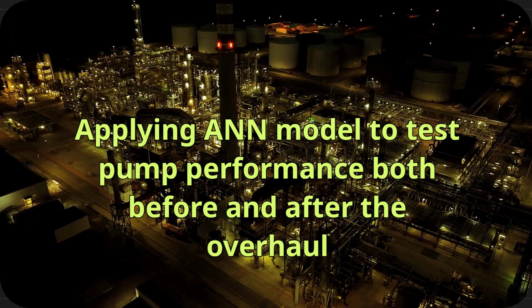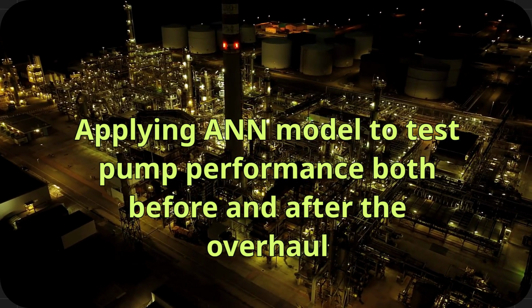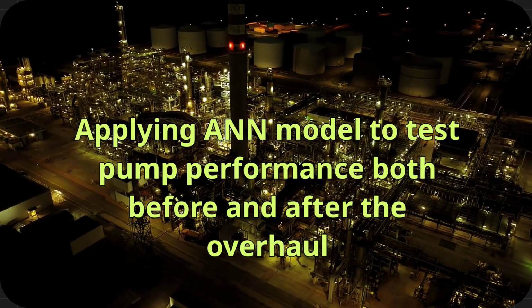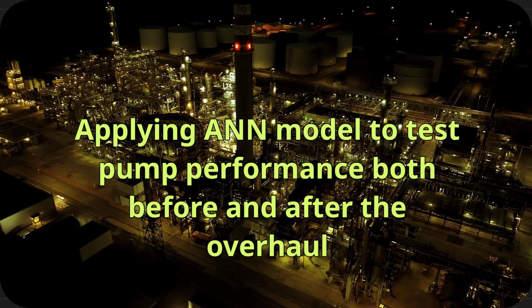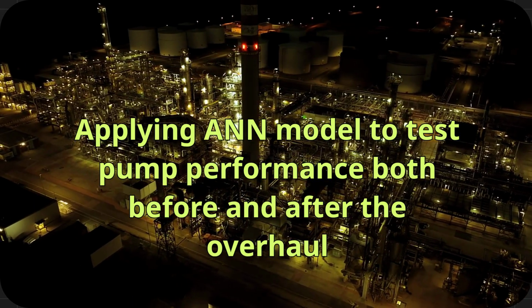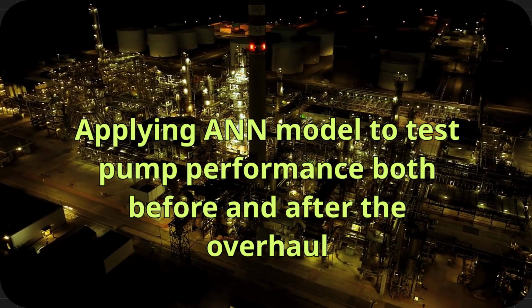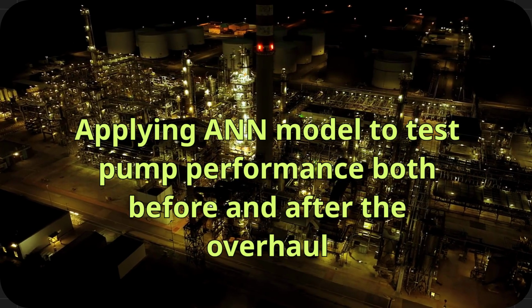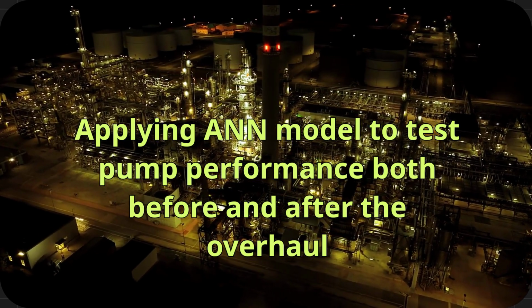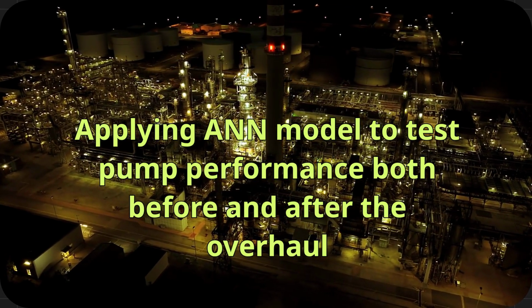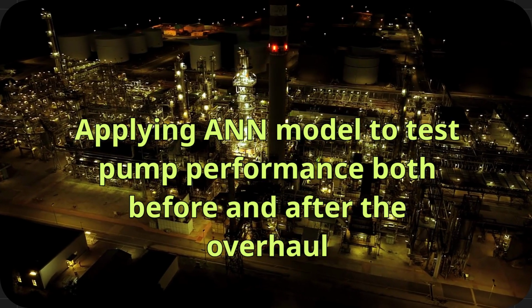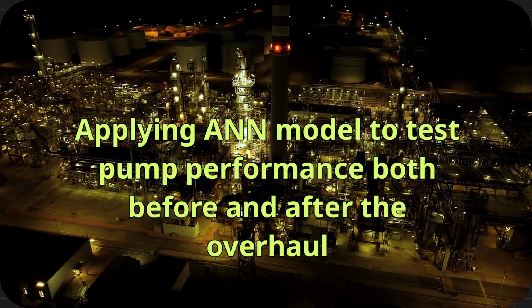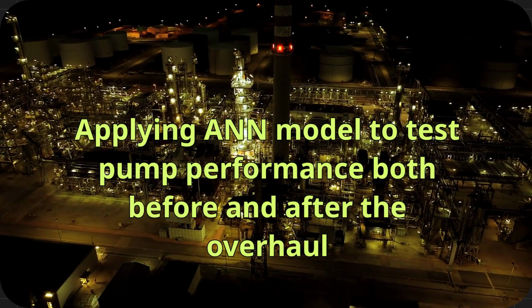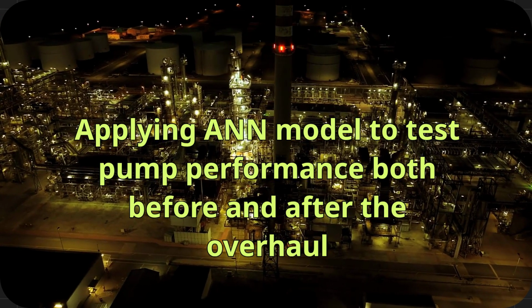The outcomes revealed several noteworthy insights. During the testing phase prior to the overhaul, the accumulated error showed only a slight upward trend. It's important to note that during this period, the pump had already accumulated a significant number of operating hours, much higher than those seen during the training period. This discrepancy could account for the mild increase in the slope of the error curve.